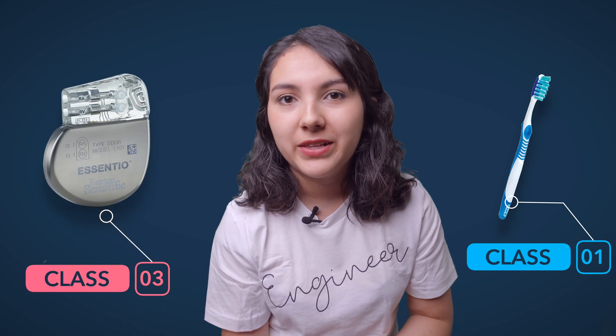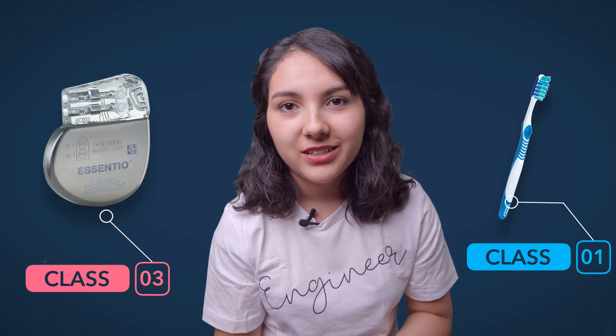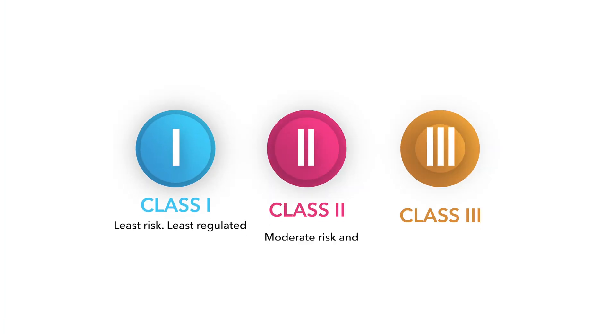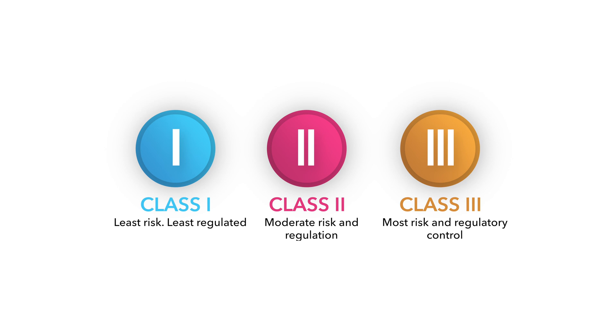For example, the FDA is not going to review a toothbrush the same way that it reviews a pacemaker that is implanted near your heart. This is why it's very important to first know the classification of your device. The FDA classifies medical devices in three main classes: class 1, 2, and 3. As the class number increases, so does the risk associated with it.